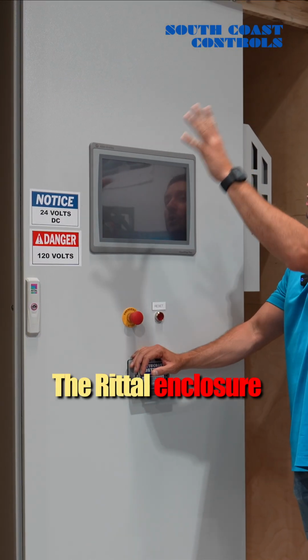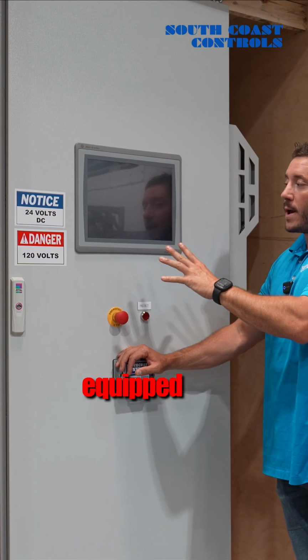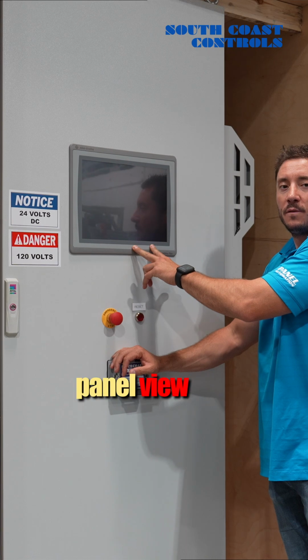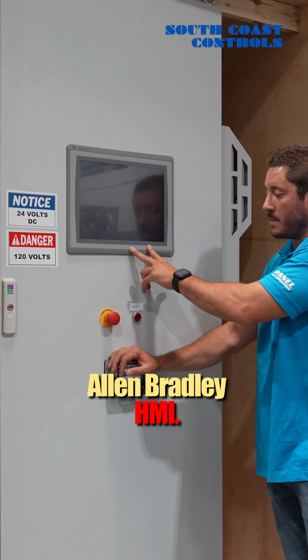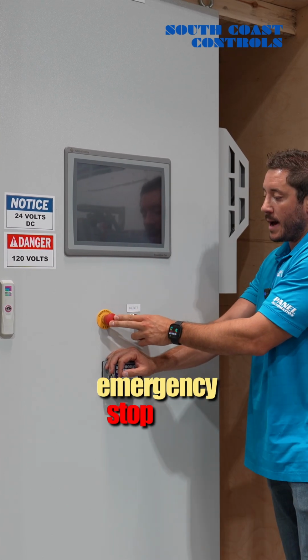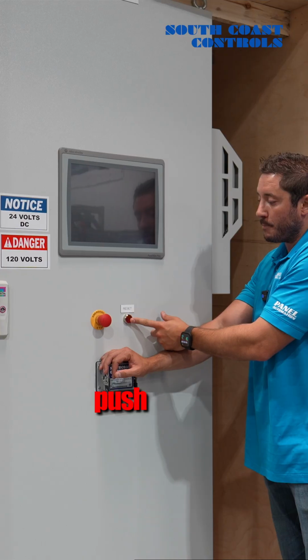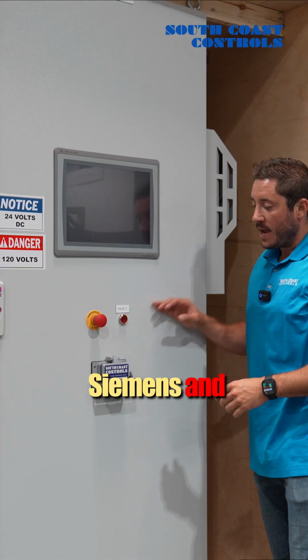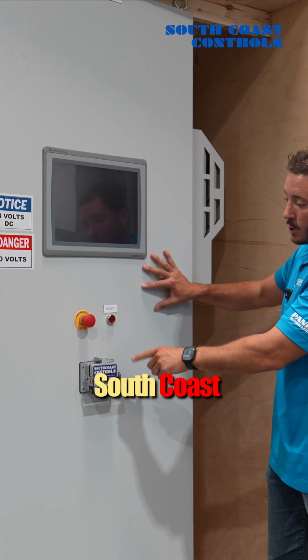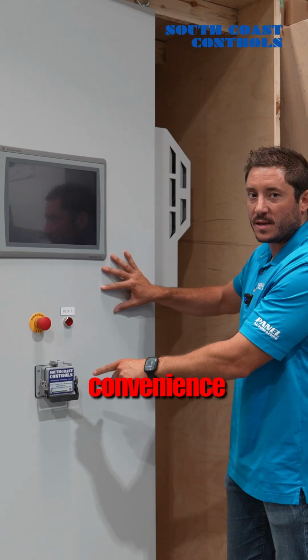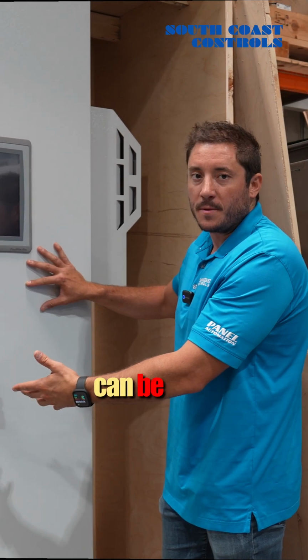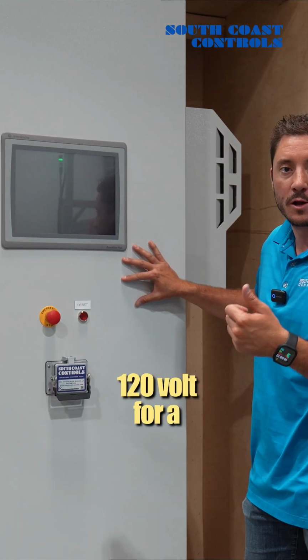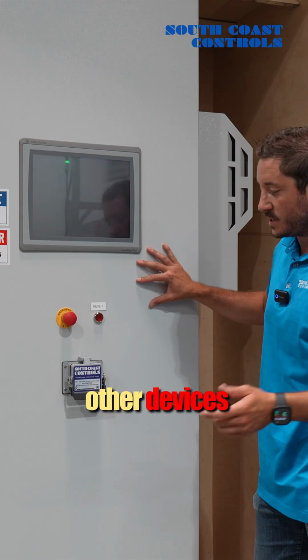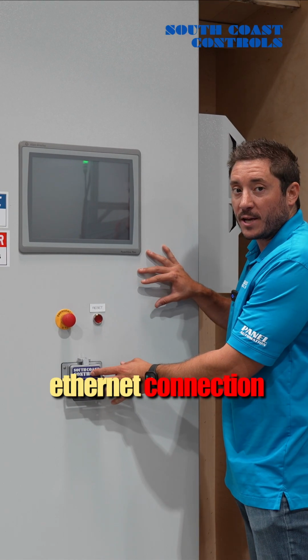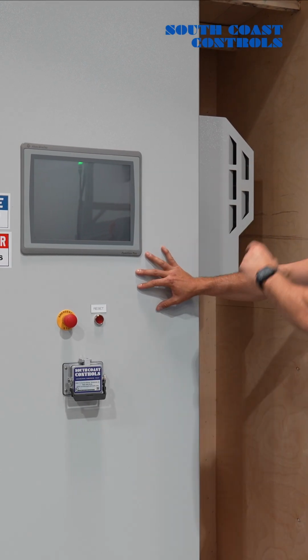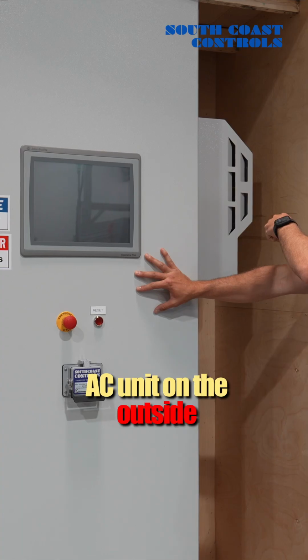The Rittal enclosure on the outside door is equipped with a 15-inch PanelView Plus 7 Allen Bradley HMI. You'll have your emergency stop from Siemens and your reset push button down here from Siemens. And it is incorporated with a South Coast Controls manufactured convenience outlet. The convenience outlet can be used to hook up 120 volt for a computer or any other devices, and any kind of Ethernet connection can be done through here. You'll also see a Rittal AC unit on the outside of the box.